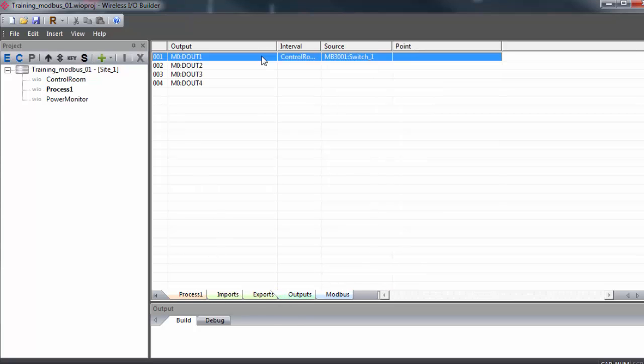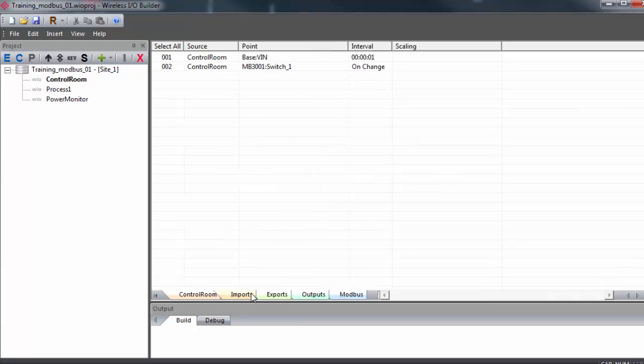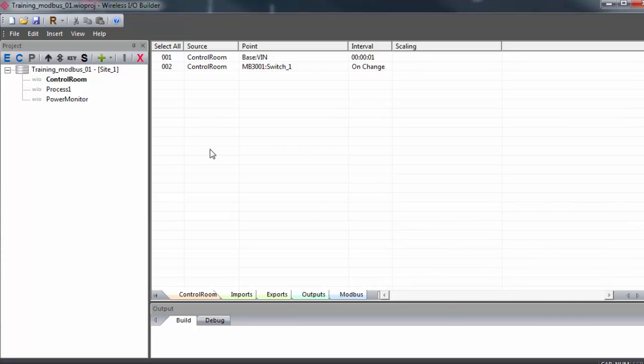Next we'll read and write data from our power monitor, which is a Modbus serial device. The gateway here does not have any I.O. modules either. It's just wired to the power monitor through an RTU connection. This gateway will need to be configured as a Modbus Master in order to poll the power monitor, which is a slave.